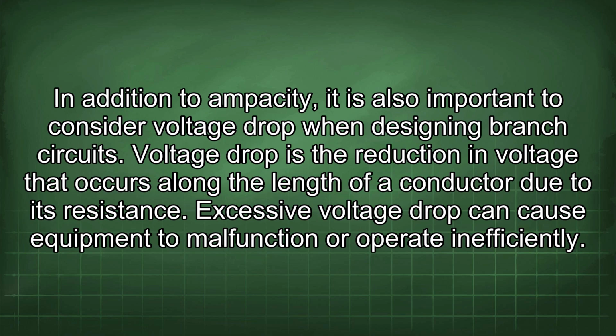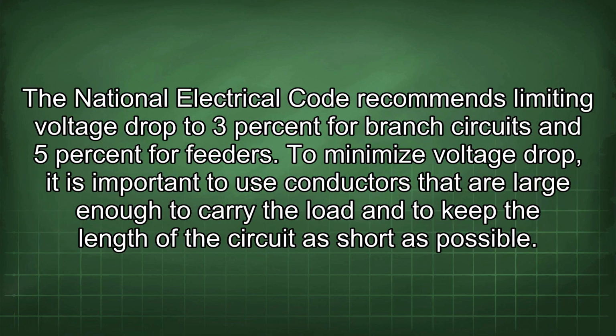Voltage drop is the reduction in voltage that occurs along the length of a conductor due to its resistance. Excessive voltage drop can cause equipment to malfunction or operate inefficiently. The National Electrical Code recommends limiting voltage drop to 3% for branch circuits and 5% for feeders. To minimize voltage drop, it is important to use conductors that are large enough to carry the load and to keep the length of the circuit as short as possible.